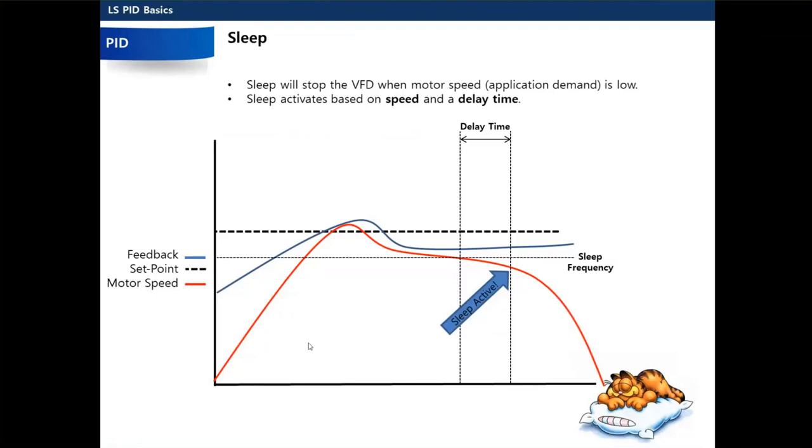So what sleep will do is it'll actually stop the VFD when the motor speed, which is the same as the application demand, is low. Think of it as like a pressure system, okay? So if you're providing water pressure for a building, everybody goes home for the day, no more flushing of toilets, nobody's turning on sinks or anything like that, the demand is low, right? The drive and the motor don't need to run anymore because the pressure is already met at set point.